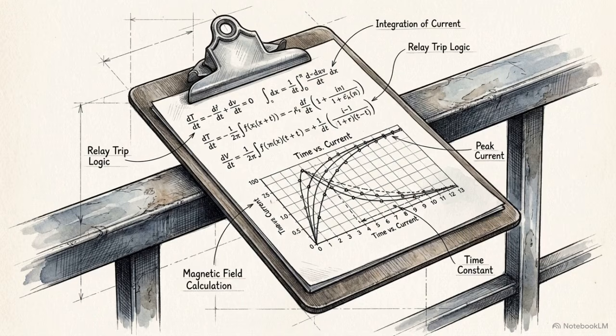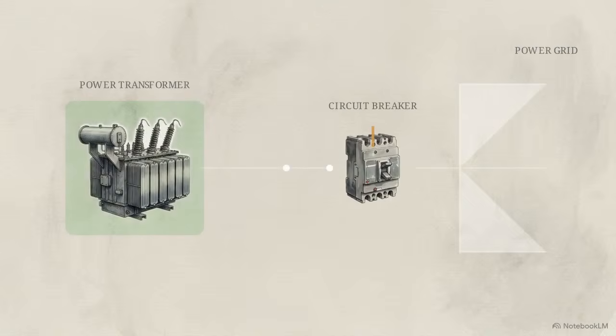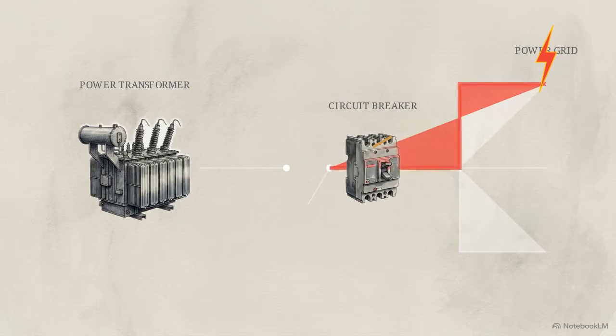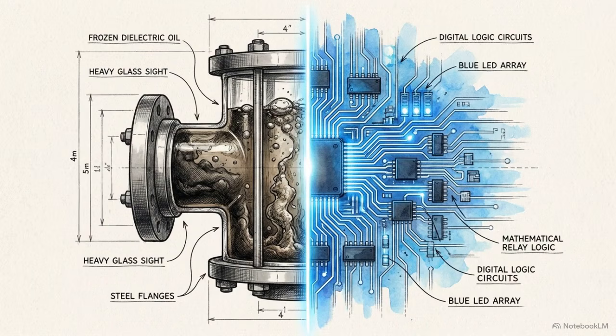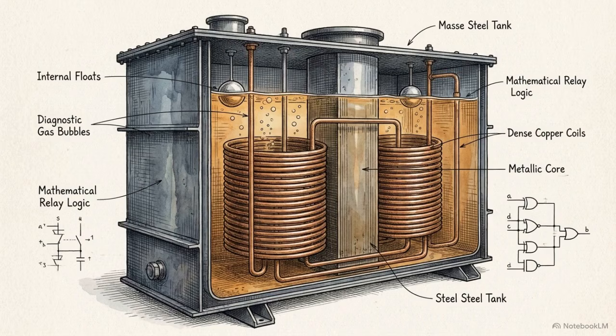The second layer involves calculating precise electrical overcurrent thresholds. This ensures the unit can instantly isolate itself from massive external short circuits on the wider power network. True grid survivability depends on bringing these two systems together. It requires bridging the gap between mechanical, gas-actuated devices and mathematical relay logic. Inside that massive tank, the transformer's core and copper windings are entirely submerged in thousands of gallons of dielectric oil.